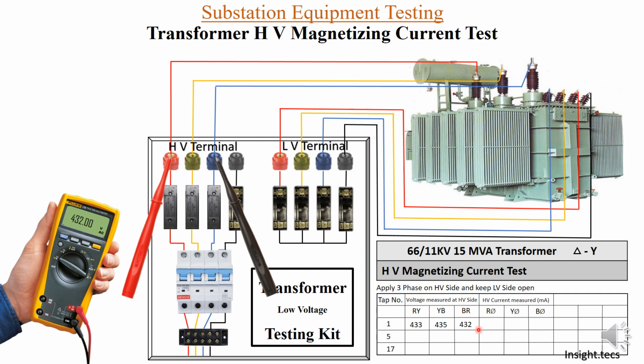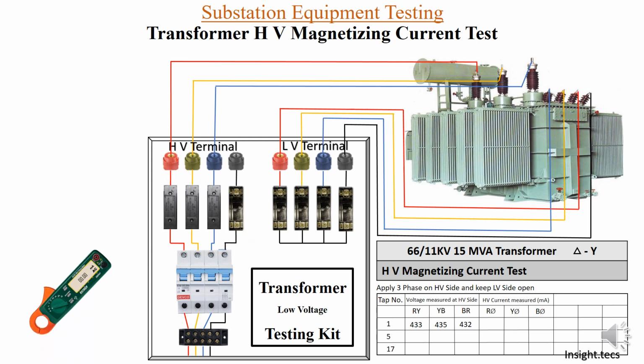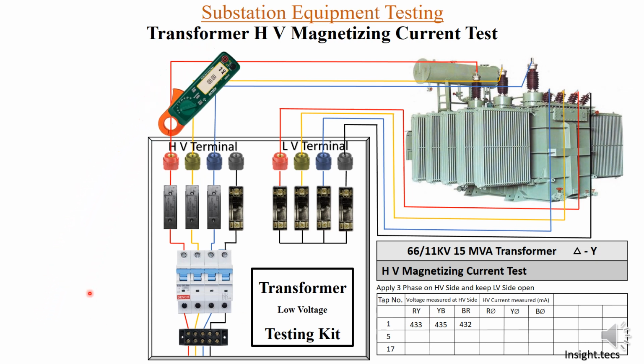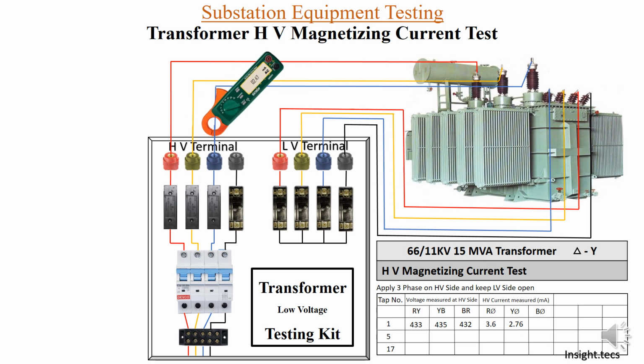Now let us see how to measure further. We have a clip-on meter to measure the current, so you have to keep the settings of this clip-on meter in milliamperes. You have to measure for HV terminals only. For R phase it is 3.60 milliamperes. For Y phase, 2.76 milliamperes. For B phase, 2.47 milliamperes. We will note it down here.